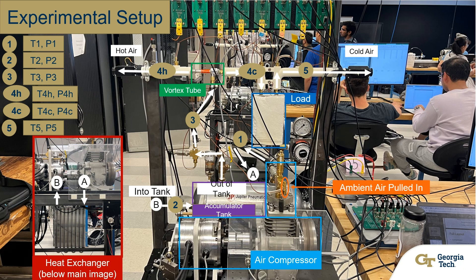The experiment is set up in lab. Highlighted in orange there is an open valve where ambient air is pulled in by the air compressor. The air compressor then allows the air to flow into the heat exchanger, which is modeled at bubble A. Once the air passes through the heat exchanger, it goes into the accumulator tank. Out of the accumulator tank, it goes up through the vortex tube where the hot air and cold air are separated. The hot air is emitted to the left and the cold air goes to the right.